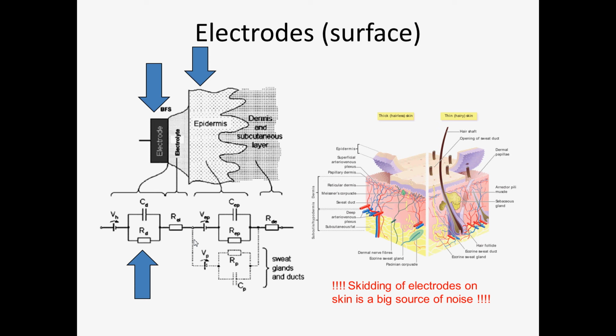They're going to cause noise. The same is true for the cap on the EEG. If you don't take care, there are some caps for EEG, I've seen them, where you actually pull the air out of the electrode so that you can use the hair of the participant to create a wet column of gel to make sure that you touch the scalp. There's nothing worse for EEG than to have a mat of hair between your electrode and the scalp. Why?